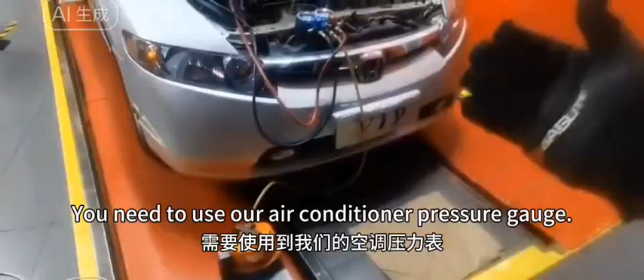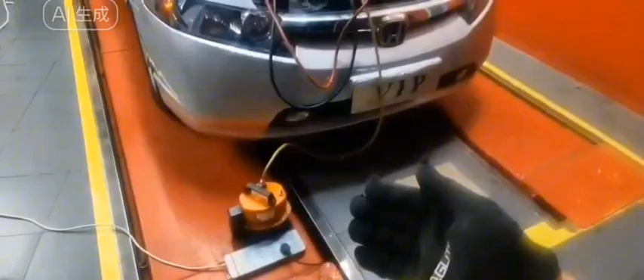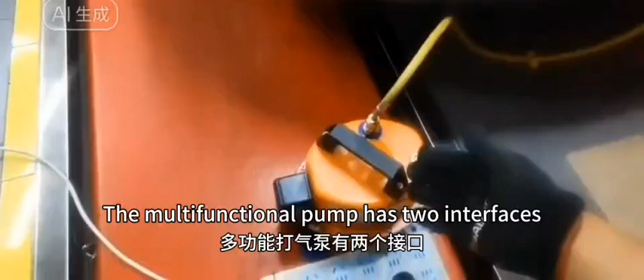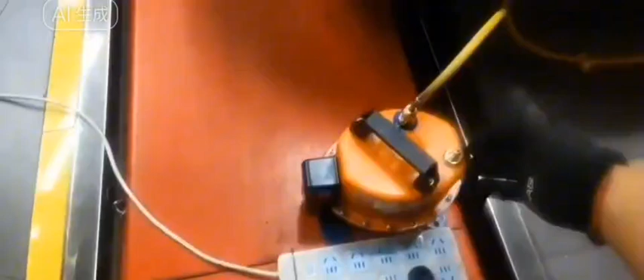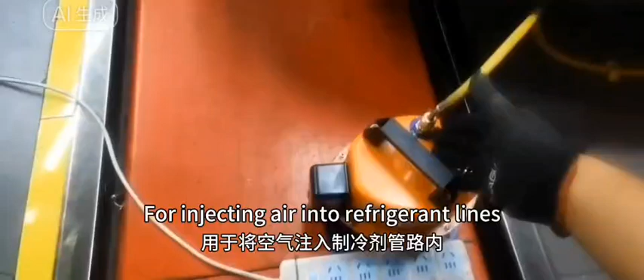When leak testing is performed on the air conditioning system, it needs to be used in conjunction with our air conditioner pressure gauge and multifunctional air pump. The multifunctional pump has two interfaces. One is the air pump interface, one is the vacuum pump interface. The air pump interface is used to inject air into the refrigerant pipeline to check for refrigerant leaks. The vacuum pump interface is used to extract air from the refrigerant line.